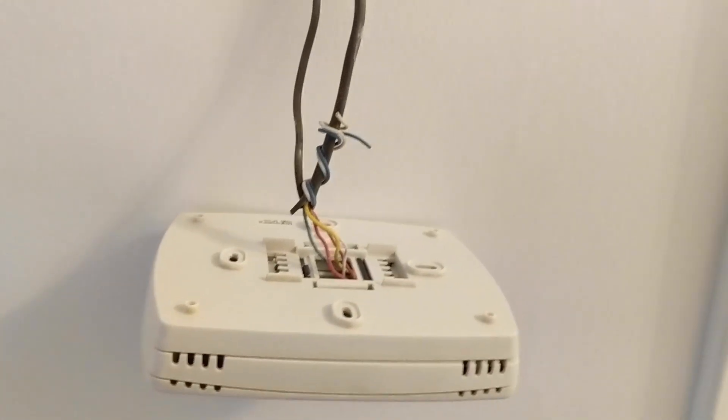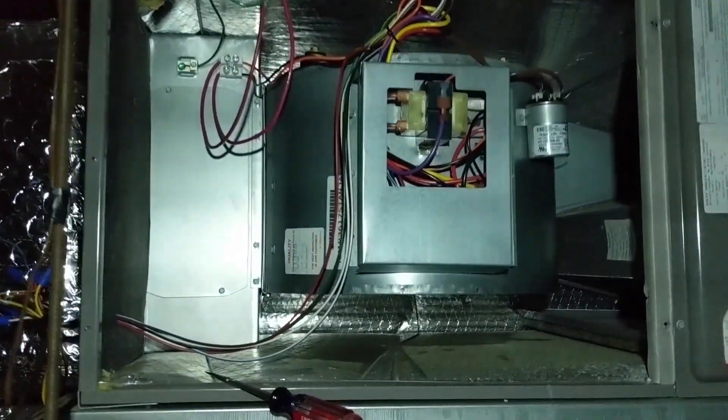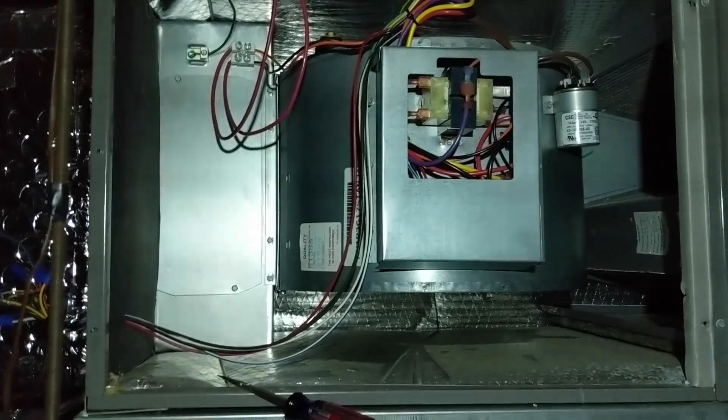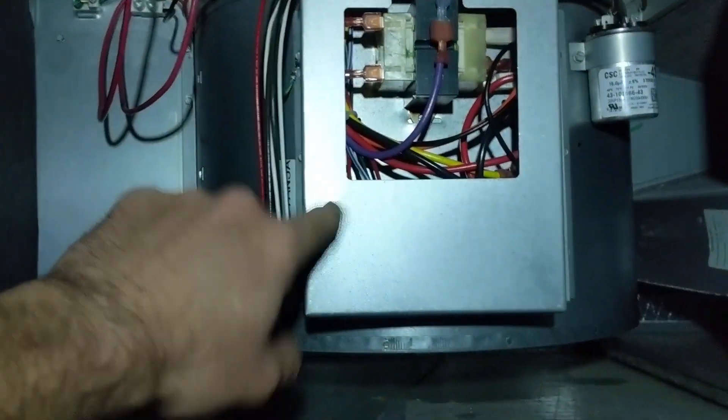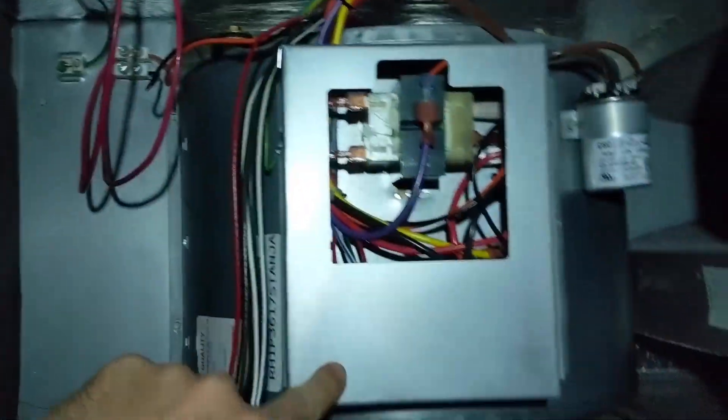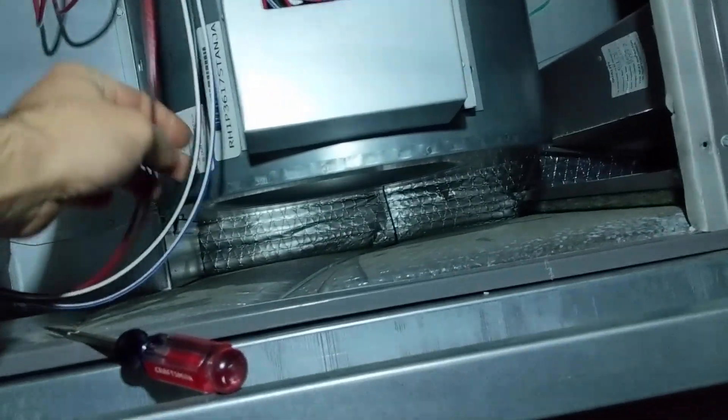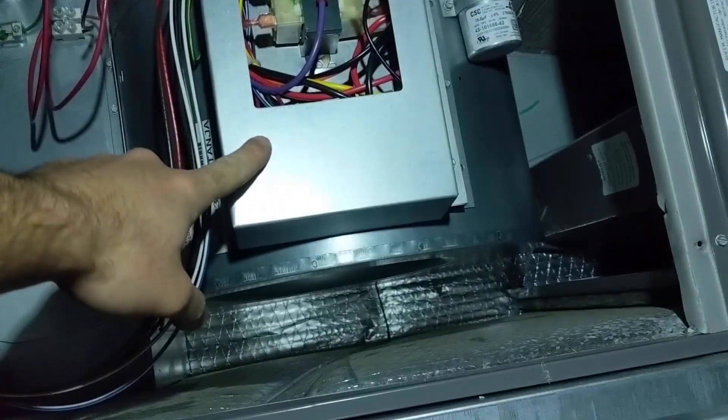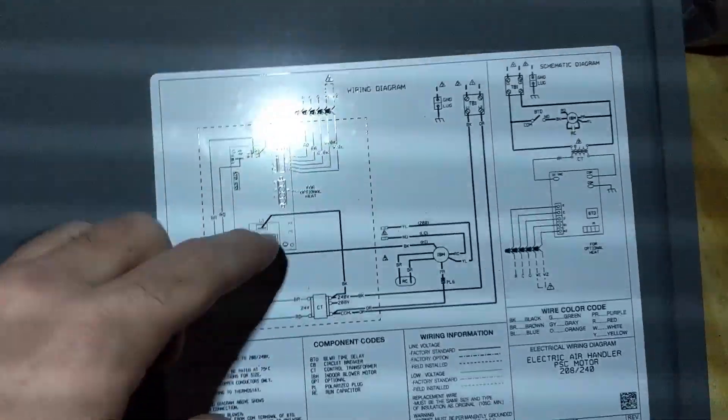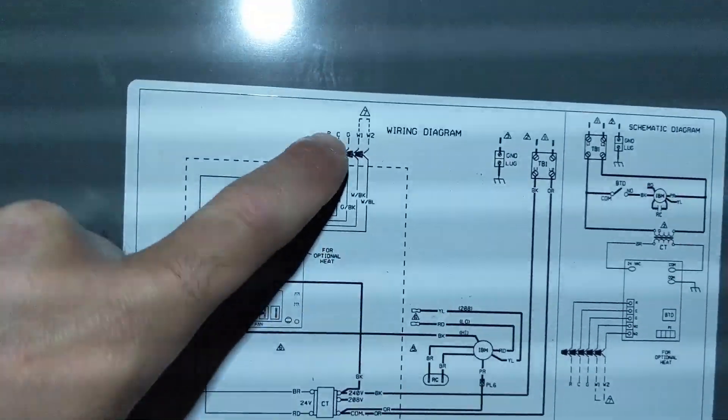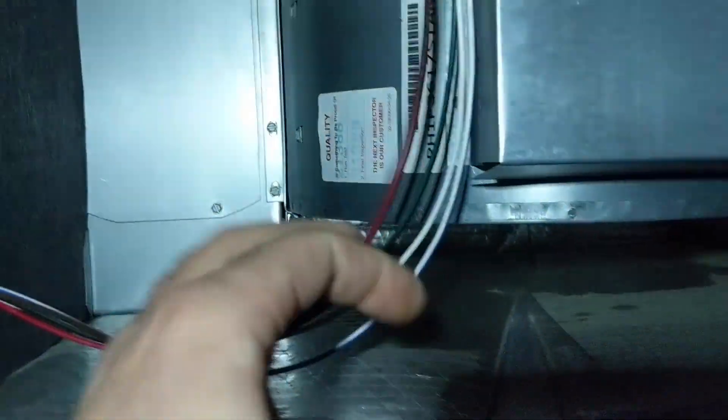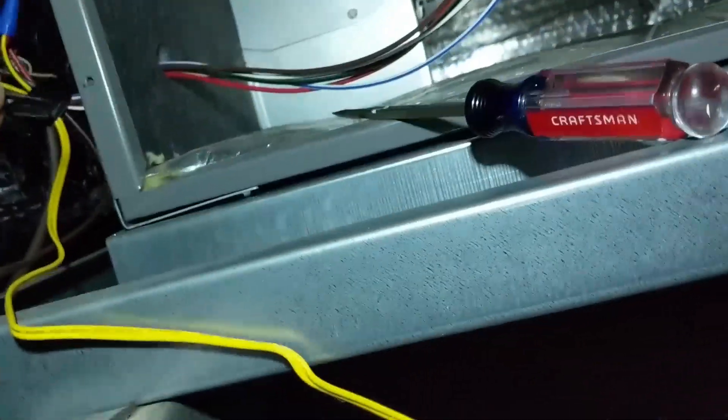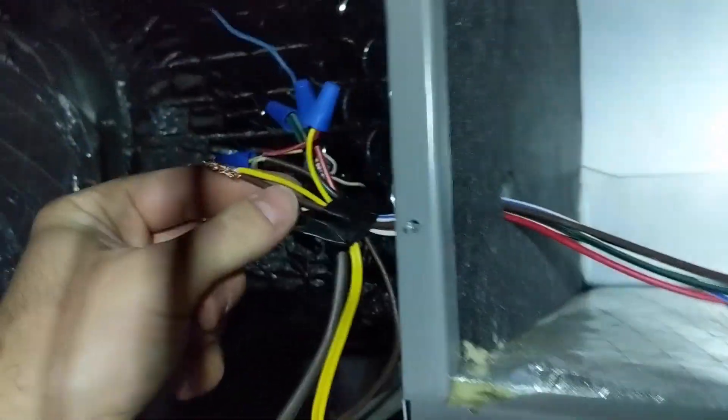I'm now up in the attic at my AC unit trying to figure out what wire would be the common wire and where it would go. I've already opened up this panel where all these wires are going into. I could see that there's a connection for common wire. According to this diagram, the common wire is brown coming out of the unit. There was no common wire going to the thermostat; however, the common wire is going to this yellow wire which is one of the wires going to the overflow float switch.